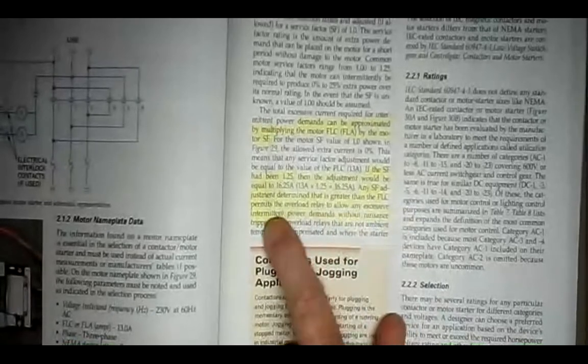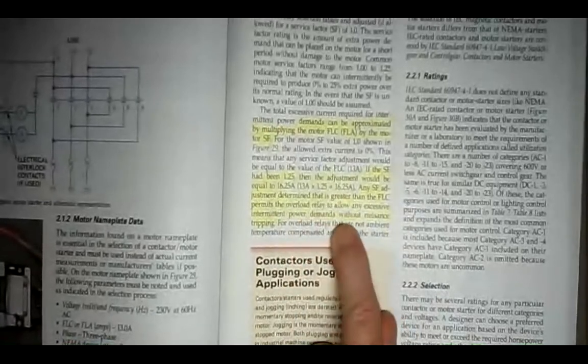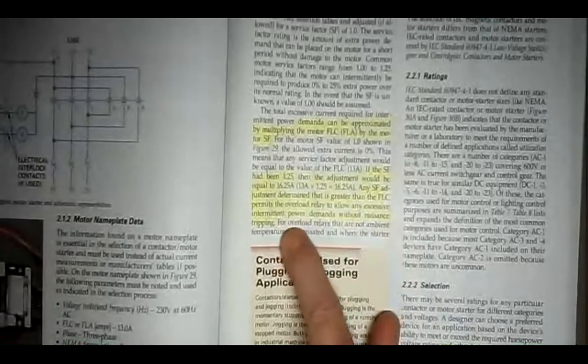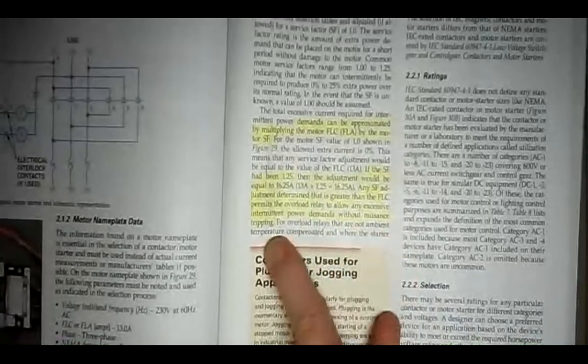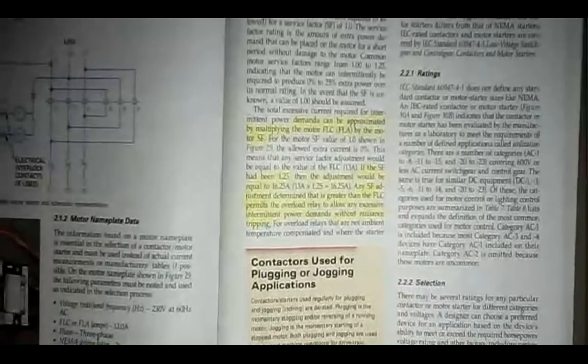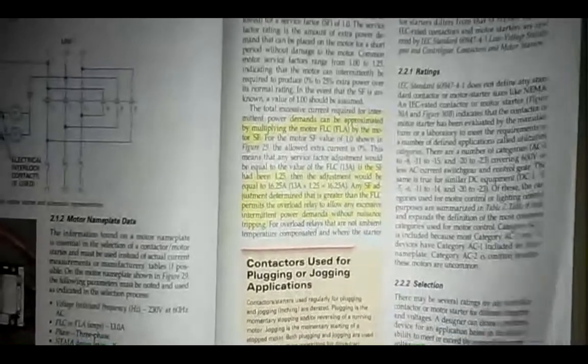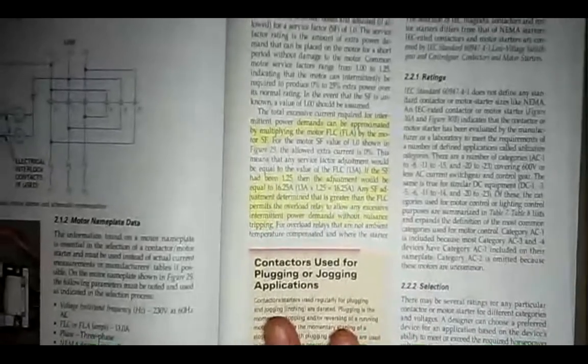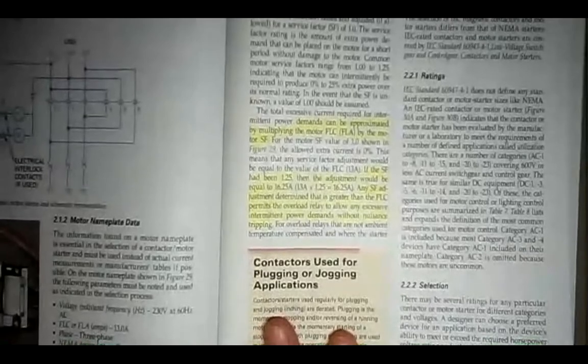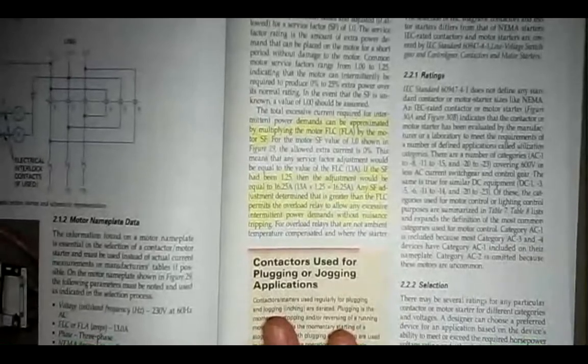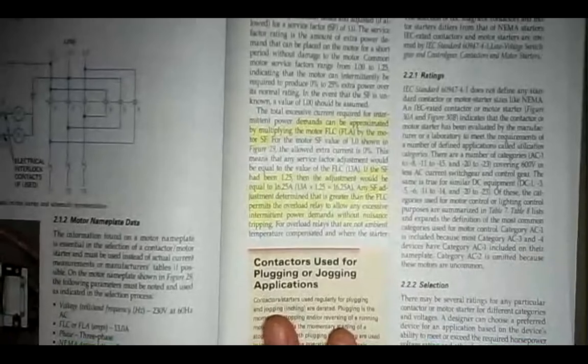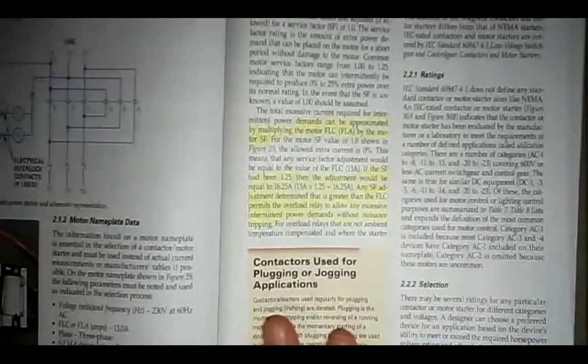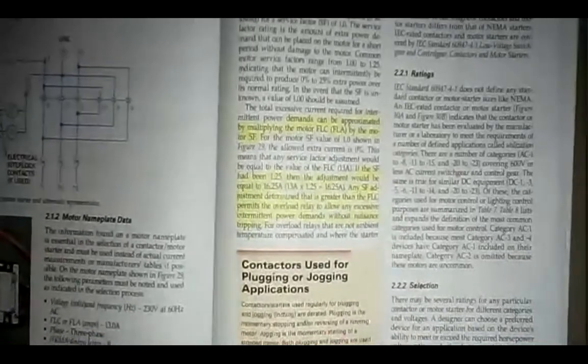Any service factor adjustment determined that is greater than the full load current permits the overload relay to allow any excessive intermittent power demands without nuisance tripping. So that way, if the motor is crushing rock or something like that, and it's going to be under load, under stress momentarily, you can allow it to go up to 25% over, and it won't trip the overload relay.